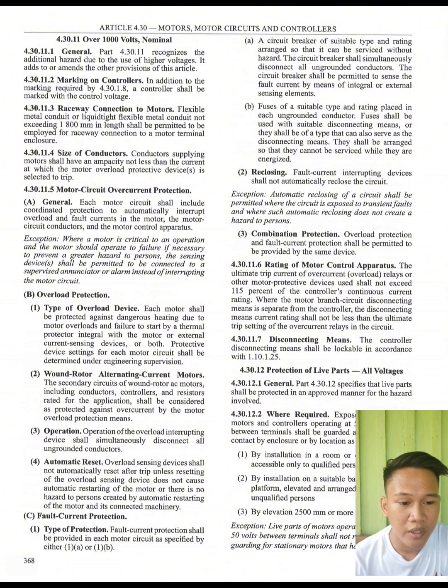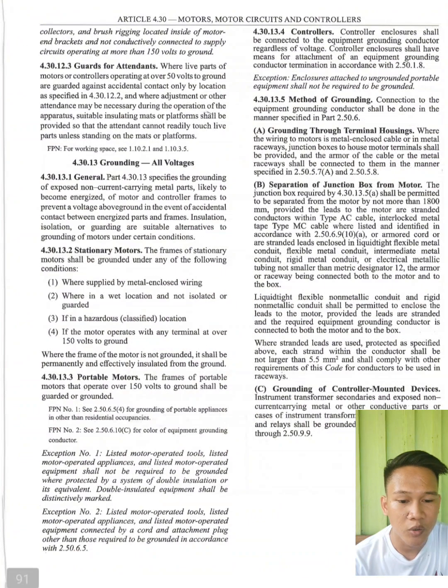One exemption is: live parts of motors operating at more than 50 volts between terminals shall not require additional guarding for stationary motors that have commutators, collectors, and brush rigging located inside of the motor-end brackets and not conductively connected to supply circuits operating at more than 150 volts to ground. Next, we have 4.30.12.3, Guards for attendants. Where live parts of motors or controllers operating at over 50 volts to ground are guarded against accidental contact only by location as specified in 4.30.12.2, and where adjustment or other attendance may be necessary during the operation of the apparatus, suitable insulating mats or platforms shall be provided so that the attendant cannot readily touch live parts unless standing on the mats or platforms.